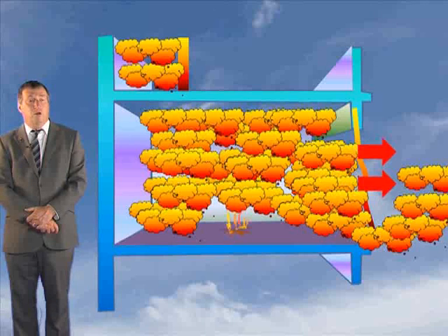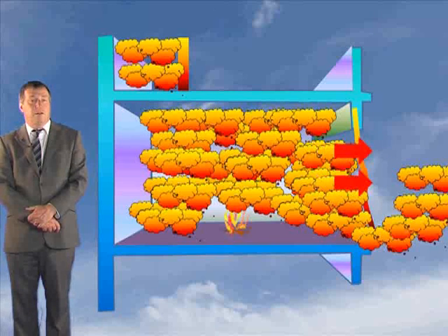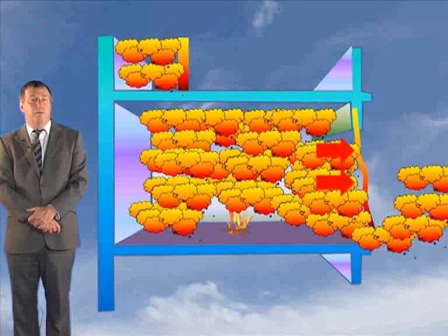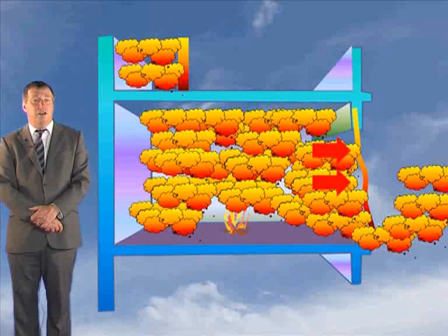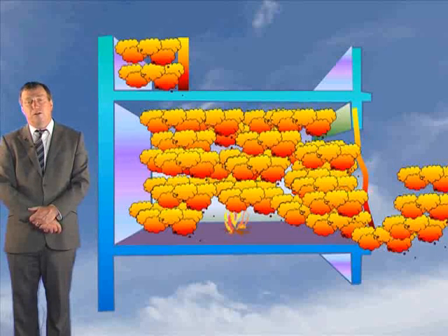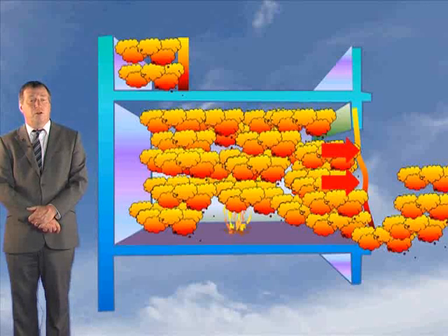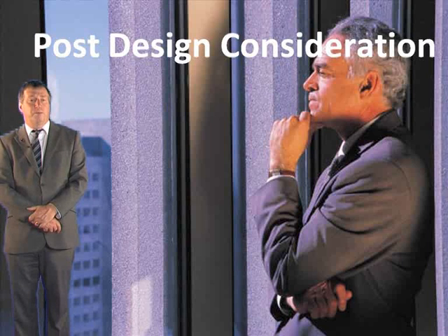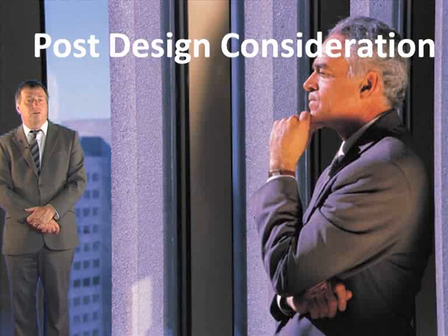It's crucially important that all smoke curtains forming part of a SHEVS are fit for purpose. This means that whatever the intended purpose of each curtain in the SHEVS design, it must be able to fulfill that purpose in its deflected position. It's therefore sometimes necessary to calculate the expected deflection of each curtain in the design and to use these calculations to specify the properties required of the curtain. So it's necessary to calculate the level of deflection and to ensure that this is taken into account. This is covered in the post-design considerations part of this course.